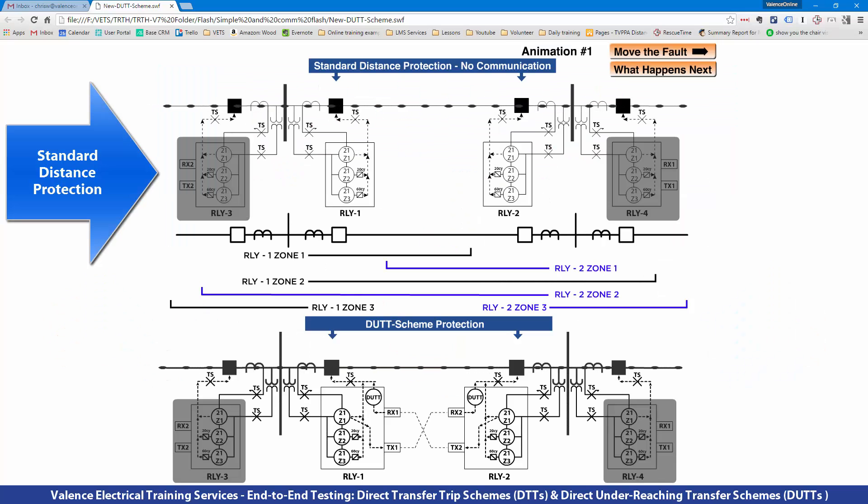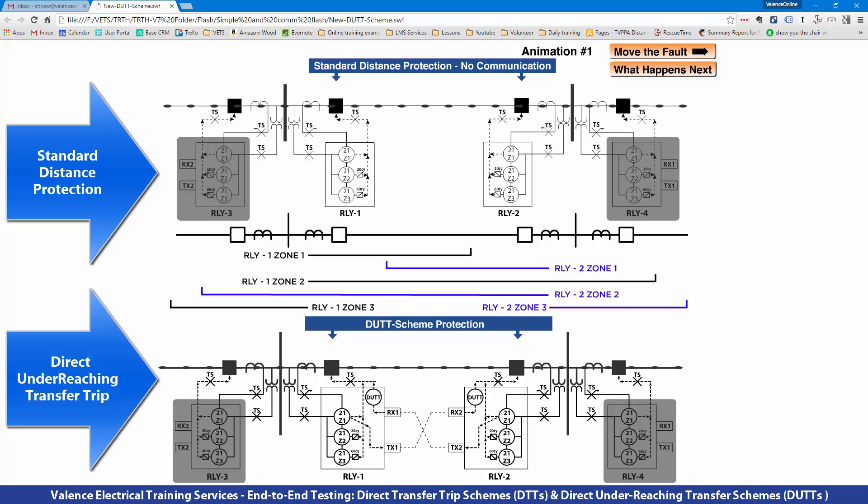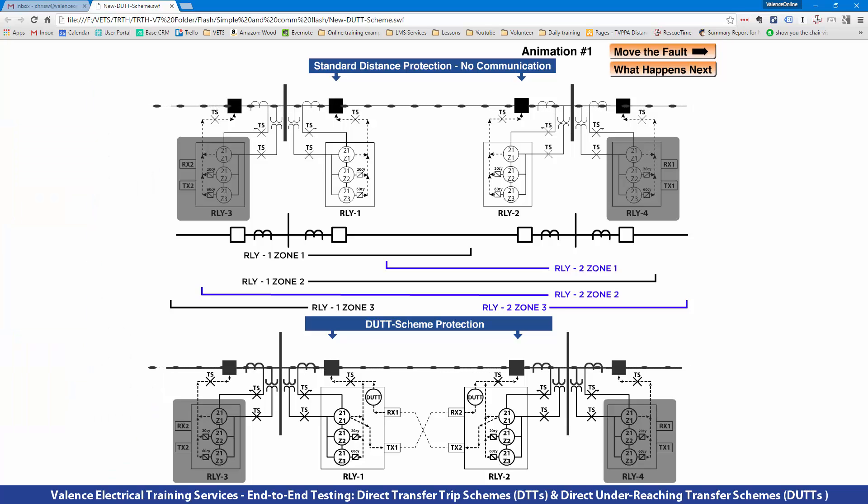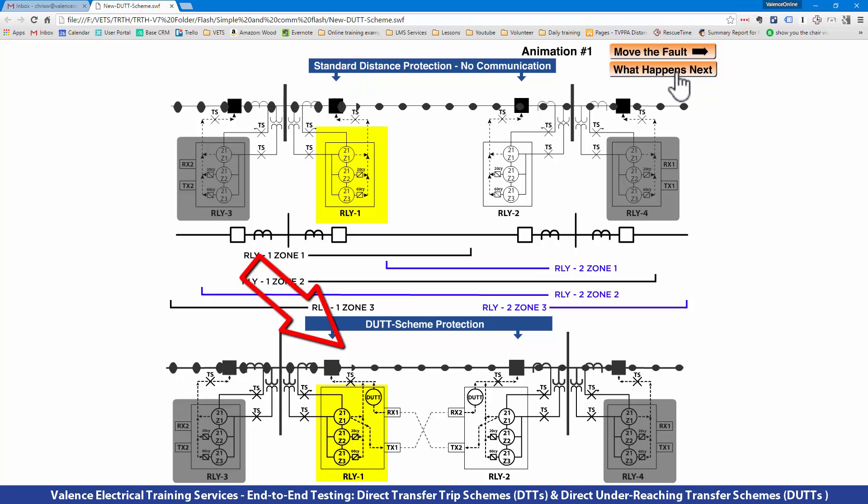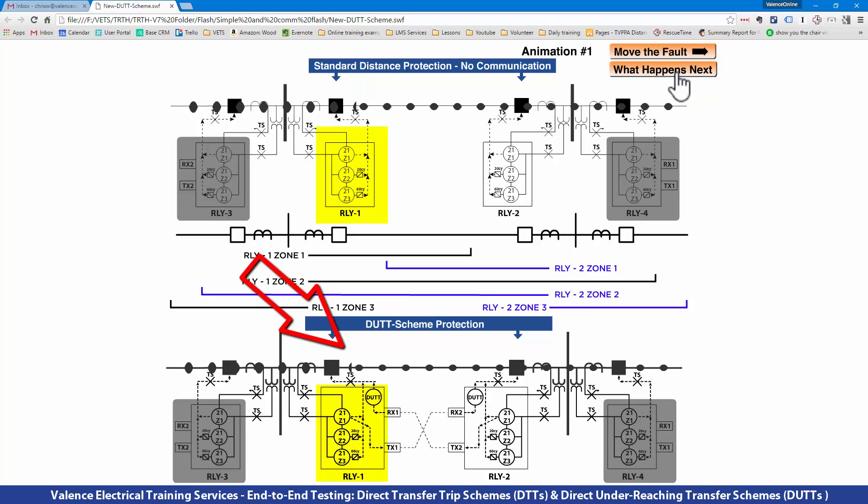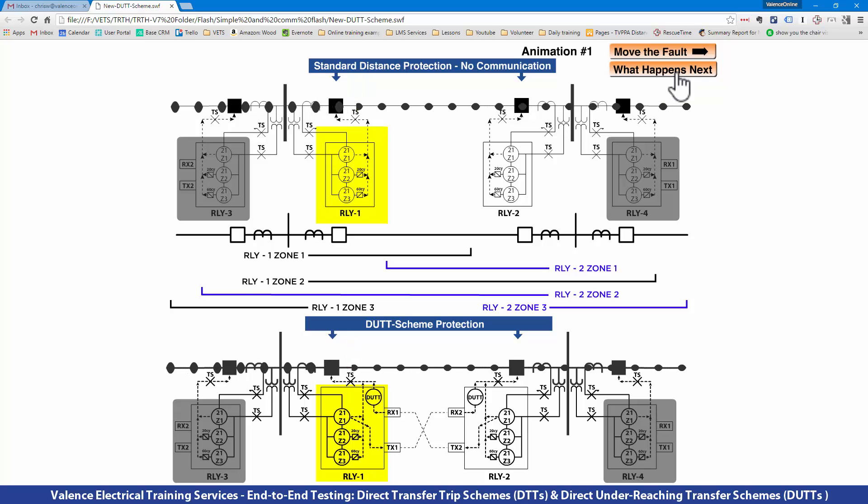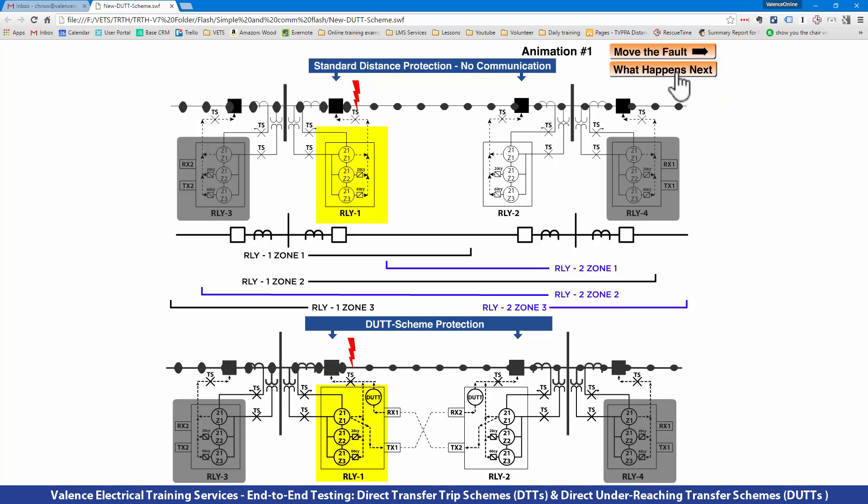The top shows the standard distance protection scheme with no communication, and the bottom shows the DUTT scheme with communication so we can see what we're gaining when we have communication-assisted trip schemes. The first thing I'm going to do is put the fault really close to Relay 1. If you watched the previous videos or have any understanding of distance protection, you'll know immediately that Relay 1 is going to see Zone 1 and Zone 2.